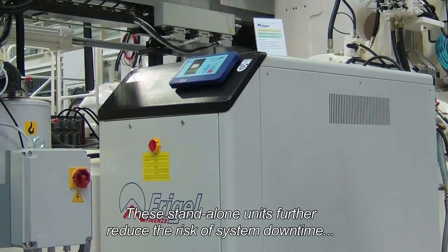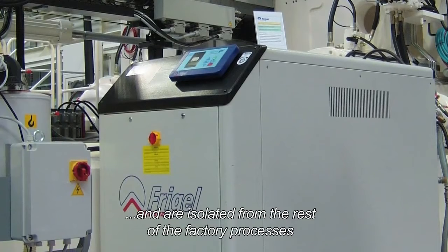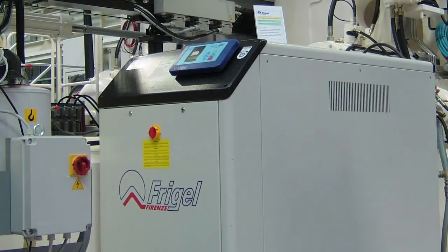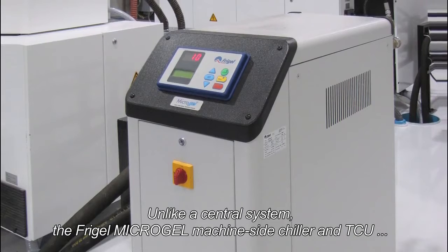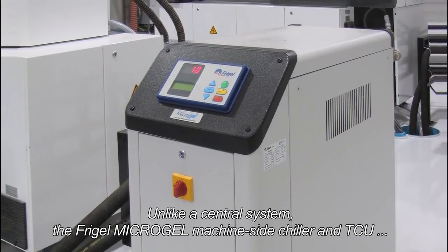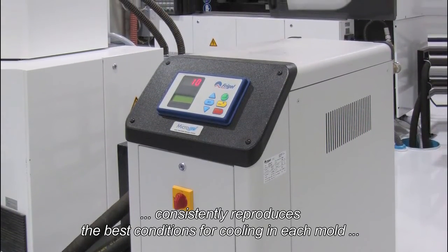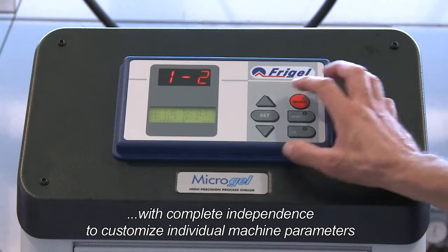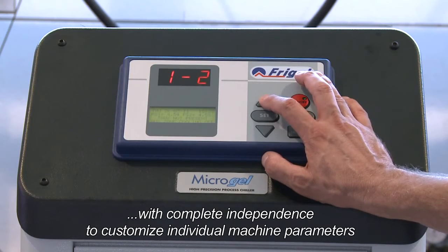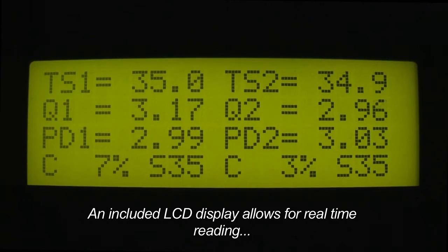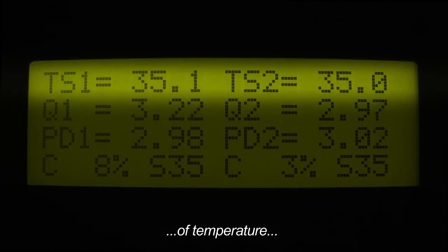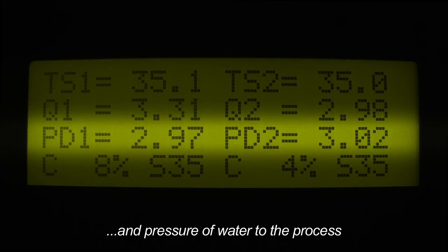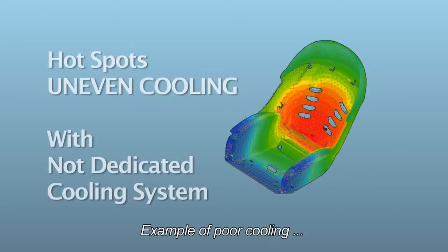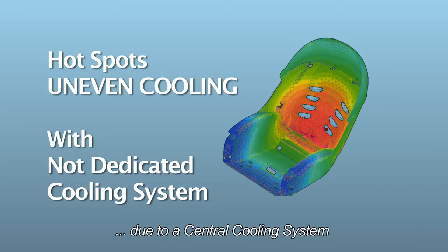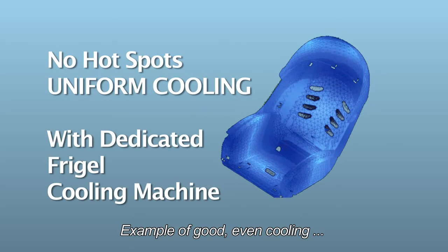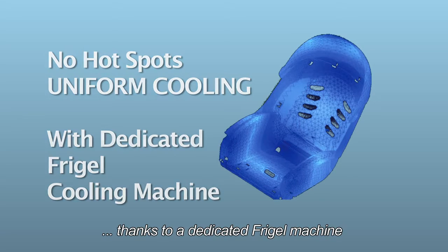These standalone units further reduce the risk of system downtime and are isolated from the rest of the factory processes. Unlike a central system, the Frigel microgel machine-side chiller and TCU consistently reproduces the best cooling conditions in each mold, with complete independence to customize individual machine parameters. An included LCD display allows for real-time reading of temperature, flow, and pressure of water to the process. Example of poor cooling due to a central cooling system. Example of good, even cooling thanks to a dedicated Frigel machine.